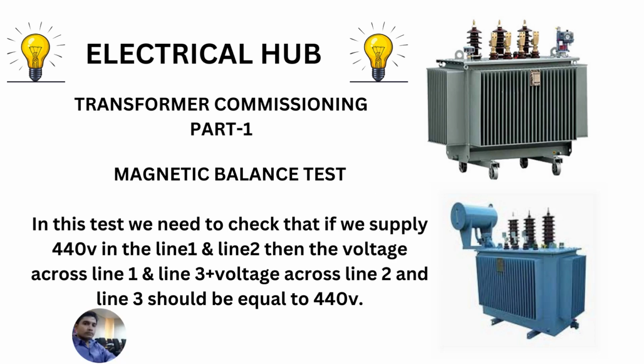In this test, we need to check that if we supply 440 volt in line 1 and line 2, then the voltage across line 1 and line 3 plus the voltage across line 2 and line 3 should be equal to 440 volt.